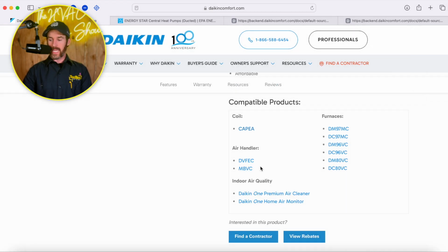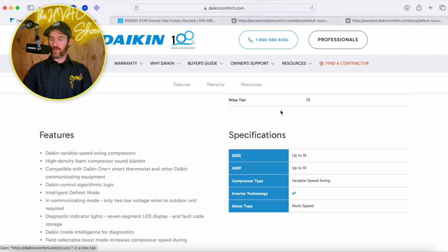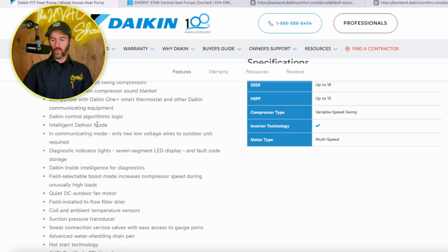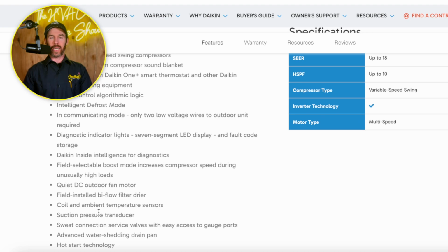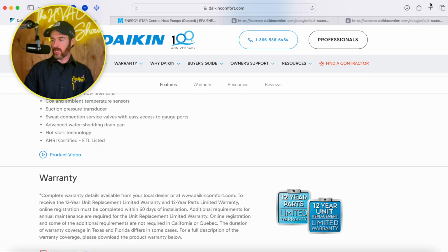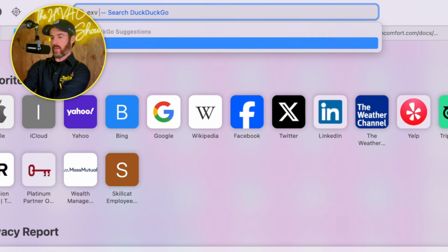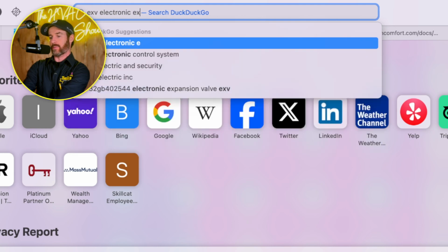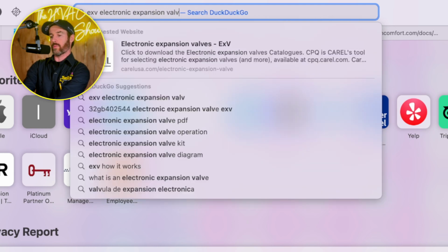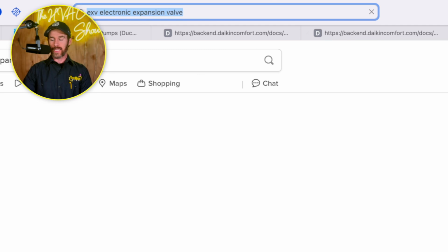The difference between this and a traditional coil is that this inverter system has several benefits, and we'll talk about some of these here. I'm spending a little bit more time on this versus the other systems because there's actually a lot more differences on the Daikin Fit versus these other systems. This system has what's called an electronic expansion valve. Normally you have a TXV inside your air handler, a device that meters the flow of refrigerant into your indoor coil.